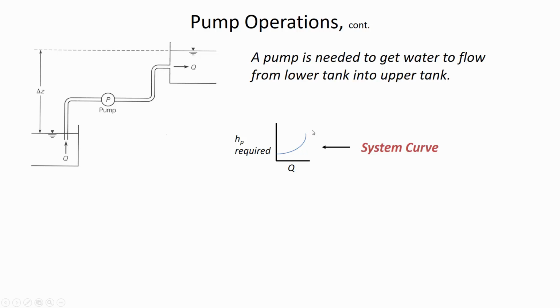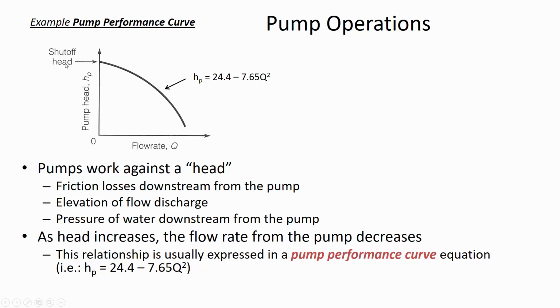Now look at the shape of that typical curve. It's in contrast to the pump performance curve. The pump performance curve was that as the flow rate goes up, the pump head decreases. Now think about why that is in a physical sense. As the flow rate goes up, the pump simply isn't able to add as much head, because think about those blades as they spin. The difference between the pressure upstream and downstream of those blades is greatest when the flow rate is small.